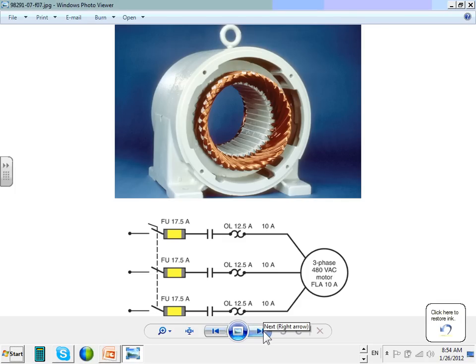This is more important, guys. This is my favorite. A motor like this one has inside it your disconnect, the fuse, overcurrent protection device, controller, overload. Typical, right? This motor is running at 10 amps, 10 amps, 10 amps. Everything is sized perfectly. This is 12.5 amps, sized perfectly based on the code, right? And this is the 17.5 fuse.